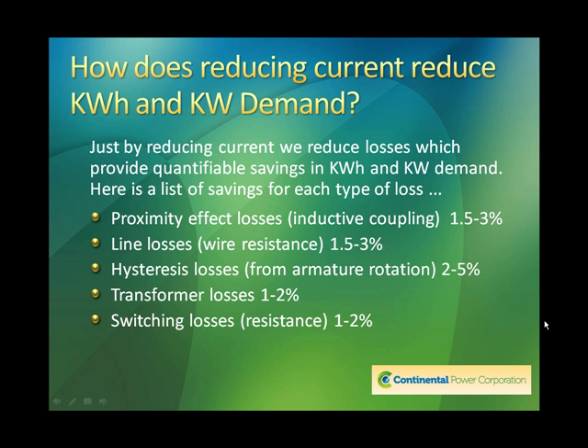Hysteresis losses from armature rotation, 2 to 5%. Transformer losses. You know, when you have a 480 volt main supply and you have a 480 to 208 volt transformer inside a commercial facility, those are not 100% efficient. Some are 95, some are 90, some are as low as 80% efficient, depending upon the type of transformer and the age. So transformer losses can total up to 1 to 2%.